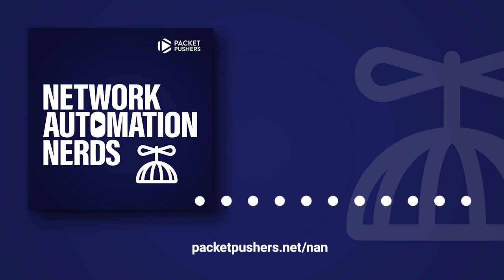The two next levels are liquid to chip, where you put the liquid right on the chip to increase capacity and density, and even full immersion cooling, where you fully immerse an entire cabinet loaded with servers in liquid. Now you're talking over 100, 150 kW to be able to do that.